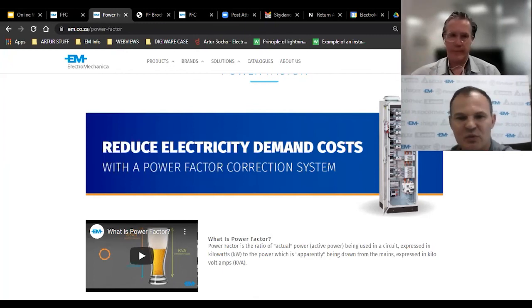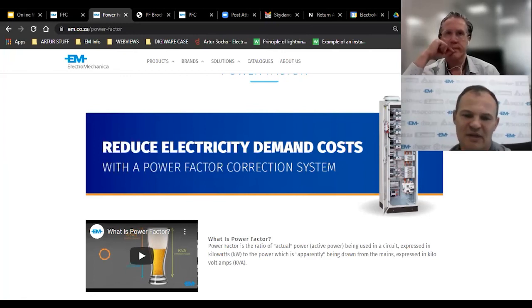One topic I didn't speak about, and I just want to quickly touch on it, is if you're looking at solar systems and your site has got bad power factor, my strong suggestion is to first sort out your power factor. First improve your inefficiencies before you go solar. Most solar guys do not understand power factor, and the power you're generating, because of your inefficiencies, is going towards losses. So what you thought you were going to get is not 100% there. Power factor normally improves that ROI if you've got bad power factor. So the ROI of solar and PF together will be faster. Okay.